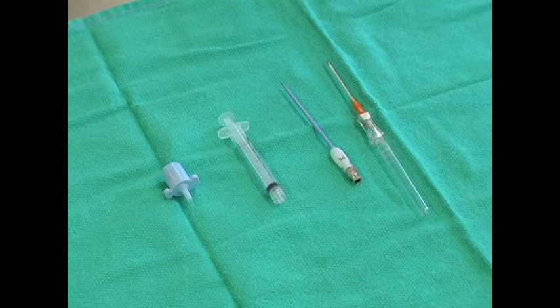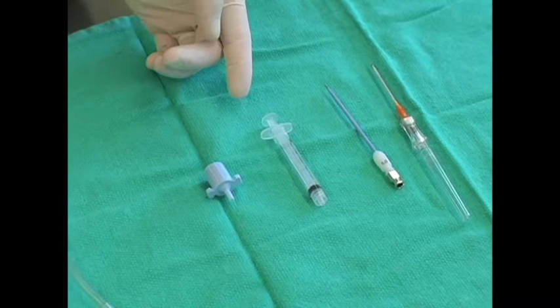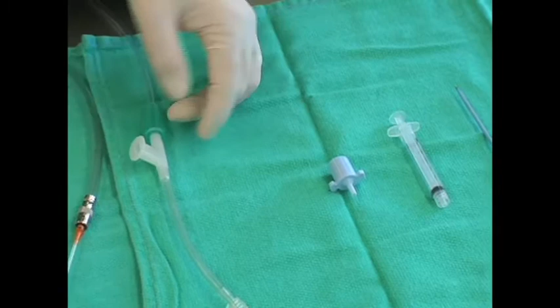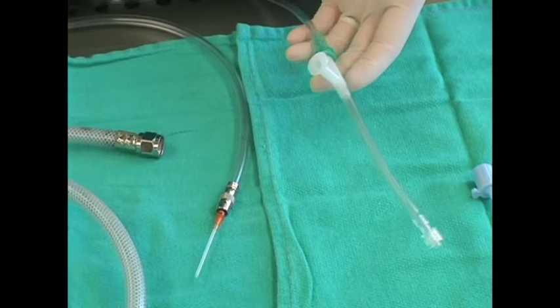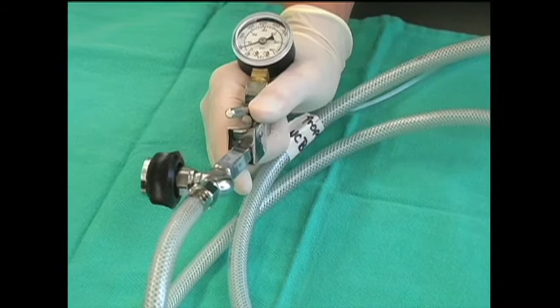Use sterile gloves as part of standard personal protective equipment used for all open procedures. Equipment required for this procedure are shown here: a 14 or 12 gauge sheathed needle catheter, a small syringe, an adapter from the end of a number 3 endotracheal tube, an oxygen source capable of delivering 50 psi connected by tubing with a Y connector or fastened with a side hole as shown here, a jet injector, and tubing for connecting to a regulated high-pressure oxygen source. A bag valve mask can be substituted, but this is not optimal.